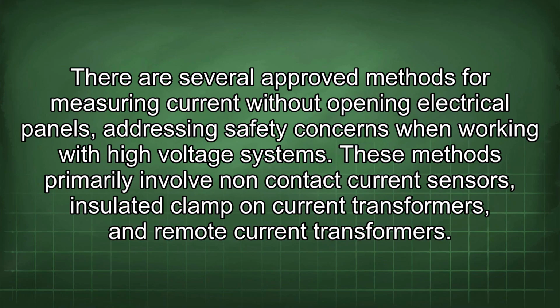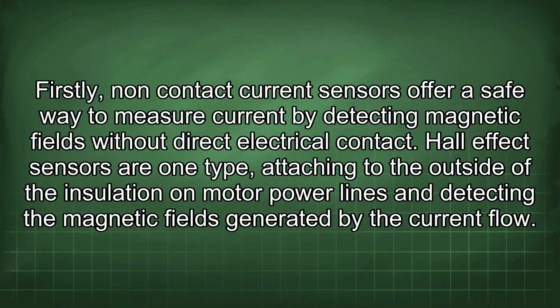There are several approved methods for measuring current without opening electrical panels, addressing safety concerns when working with high-voltage systems. These methods primarily involve non-contact current sensors, insulated clamp-on current transformers, and remote current transformers. Firstly, non-contact current sensors offer a safe way to measure current by detecting magnetic fields without direct electrical contact.